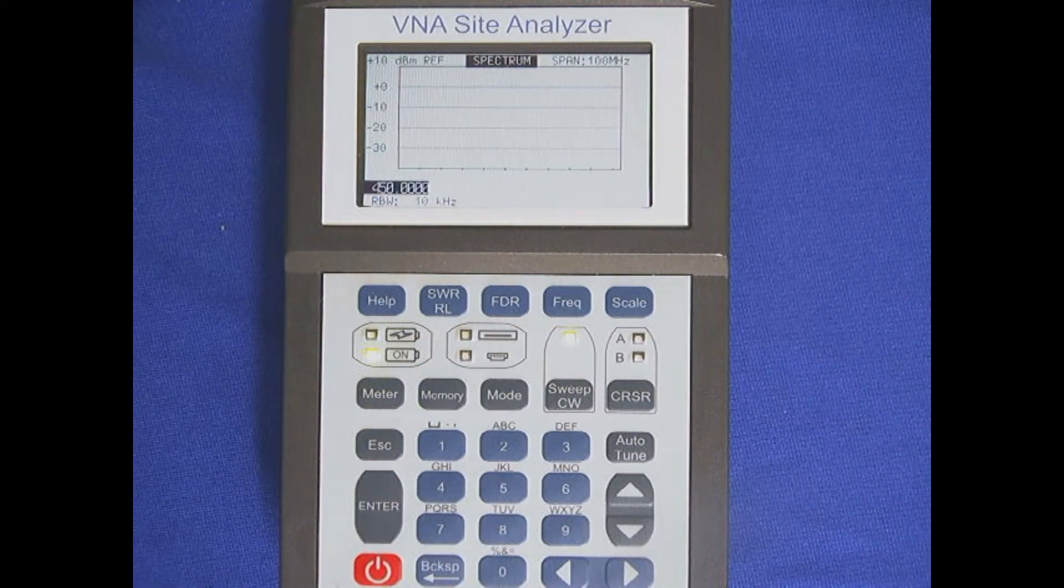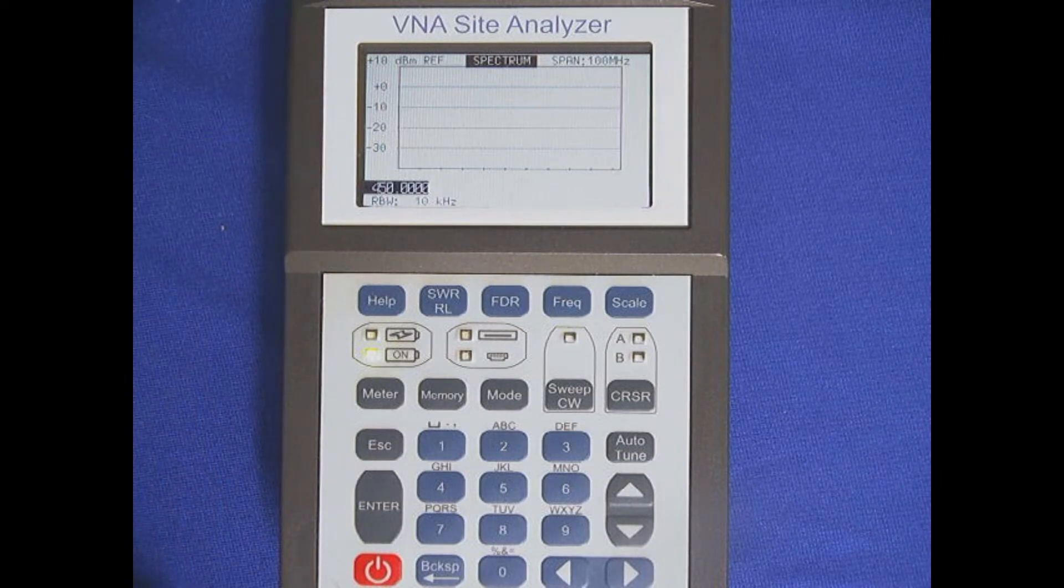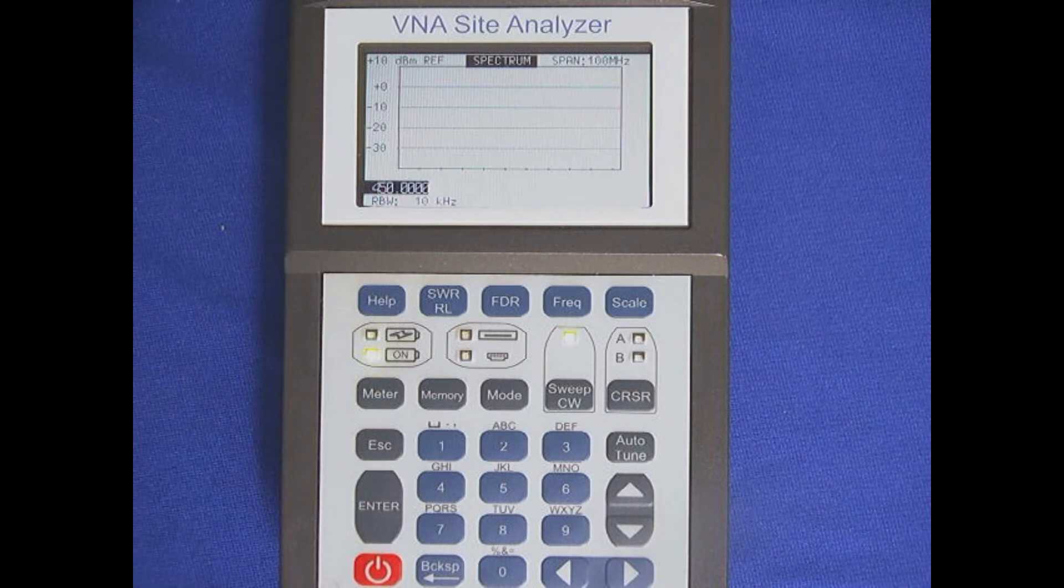Now, you need to consider when setting up the AEA Liberator Spectrum Analyzer. First, the display only has 250 points. So in a wider spread like this, a wide frequency spread, the first test is just going to give us a rough idea of where to look.